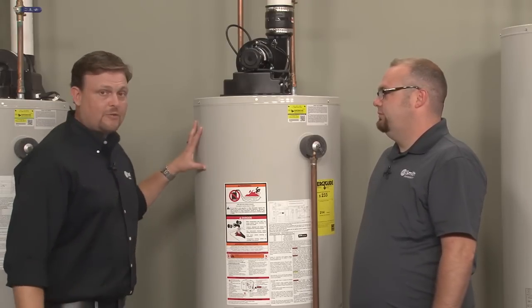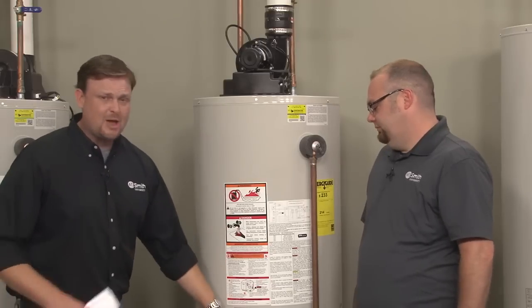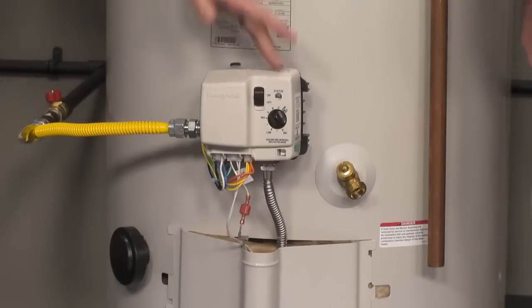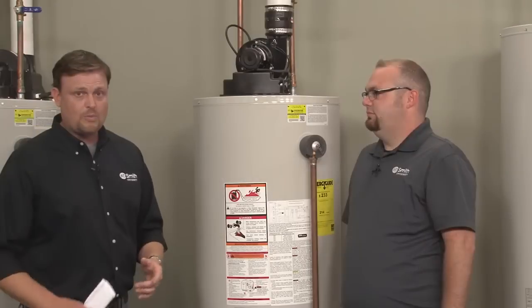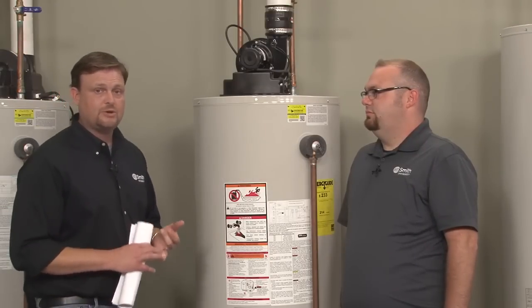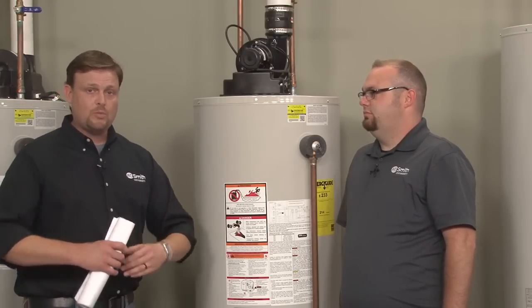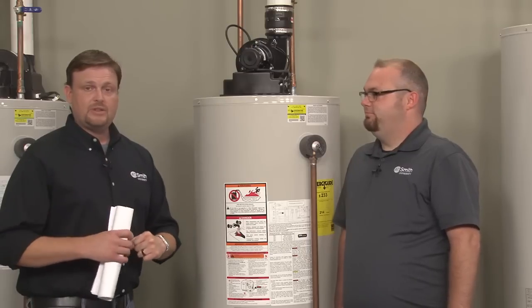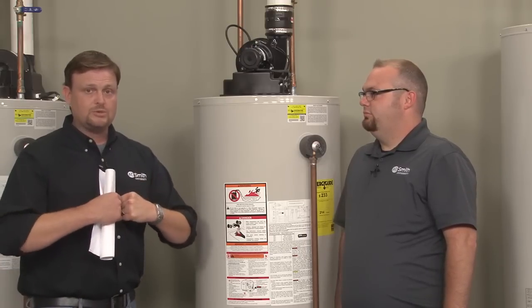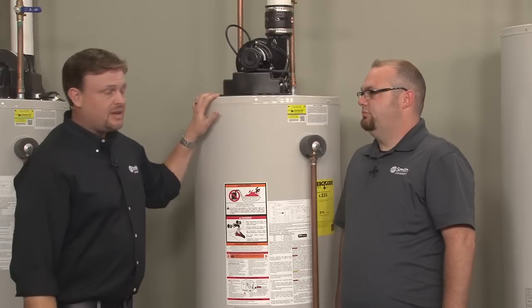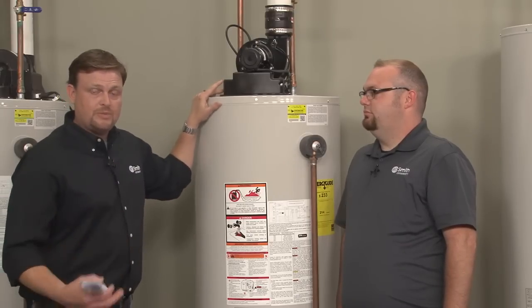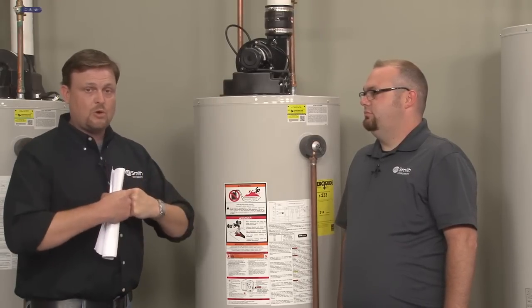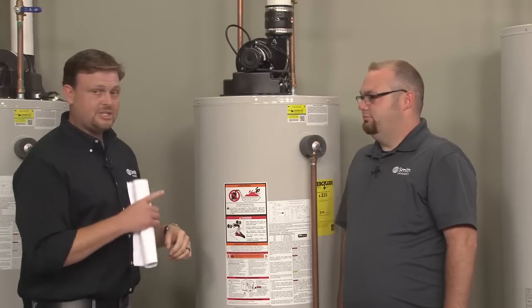So you have a call for heat. The first thing, and this happens very quickly, is the gas valve checks to make sure that the blower prover and the high vent temperature switch are in their correct states. That means the blower prover switch is going to be open and the high vent temperature switch will be closed. Once it sees that, it kicks on the blower. The pressure from the blower then closes that blower prover switch.